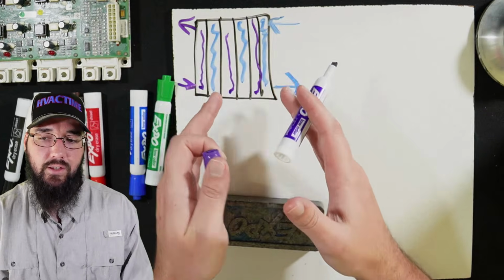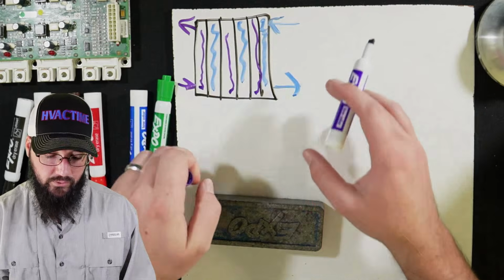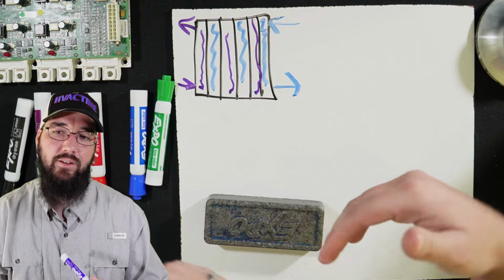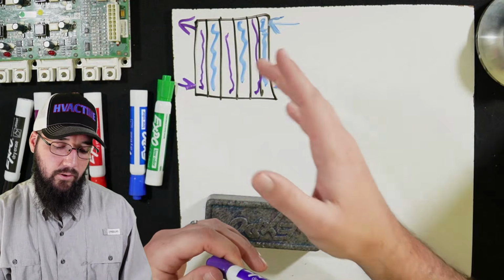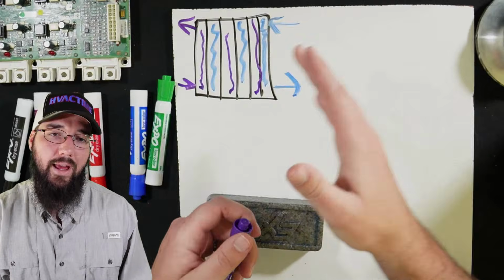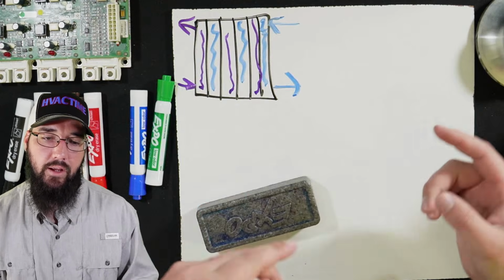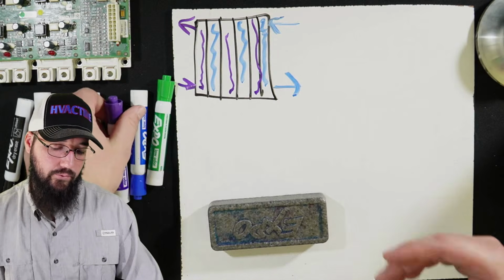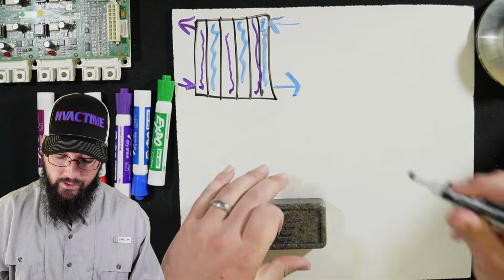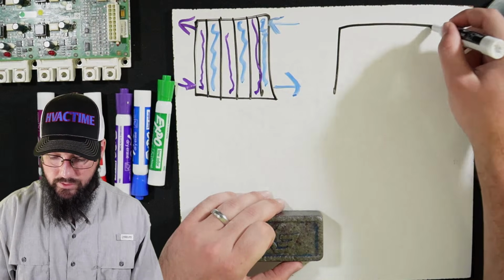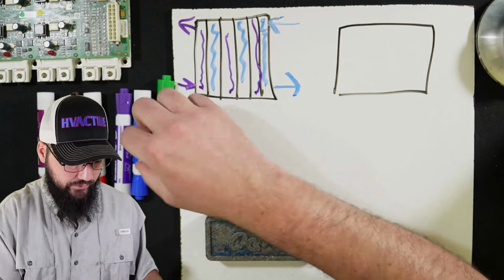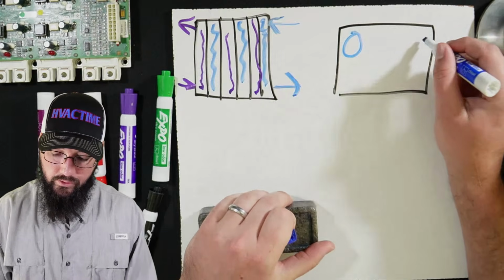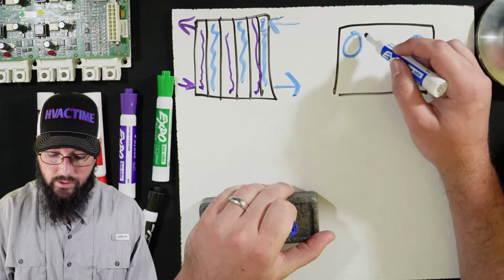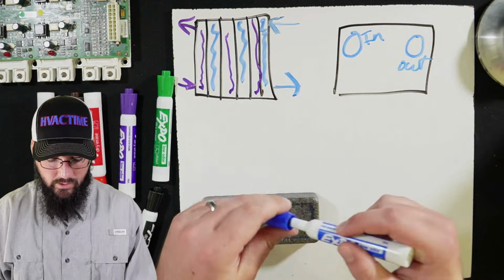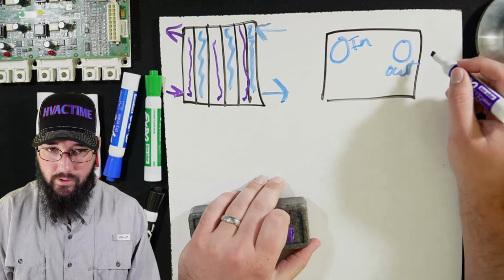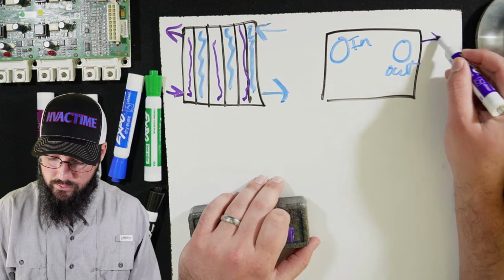There are seals isolated internally here that protect these circuits from intermixing, so the water and refrigerant don't blend. But we can still exchange heat through these plates that have corrugation to them, so that there's more surface area, and it also creates more turbulence in there for heat exchange. All right. Now for a DX shell and tube, we're actually going to have water coming into the shell side. Okay, so water in, water out, and refrigerant is going to be coming in through the end bell. So there should be a suction line in.